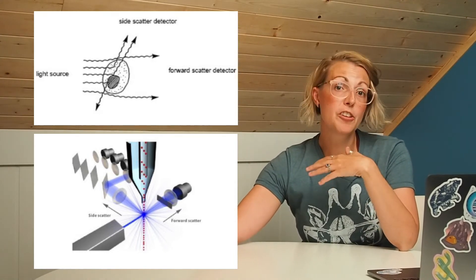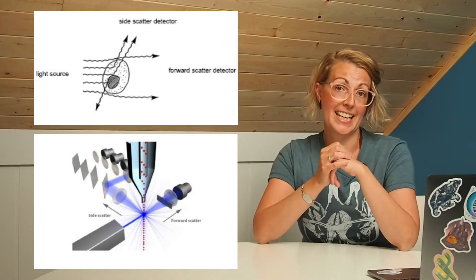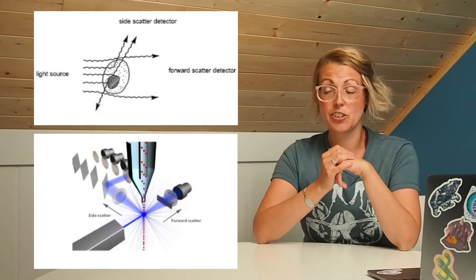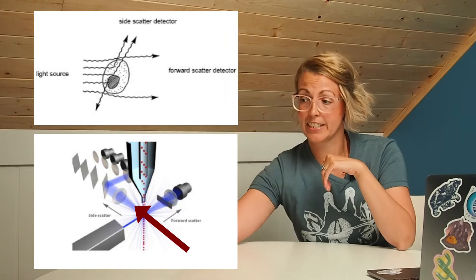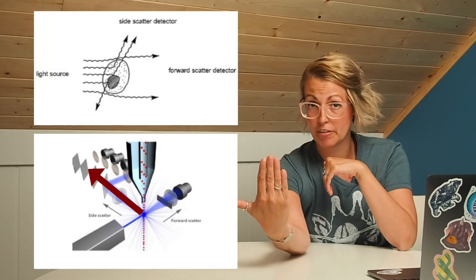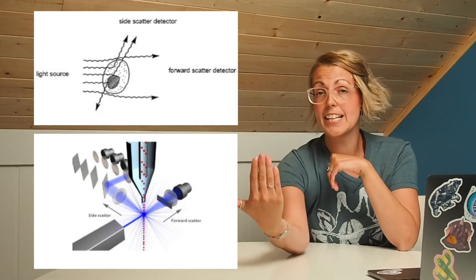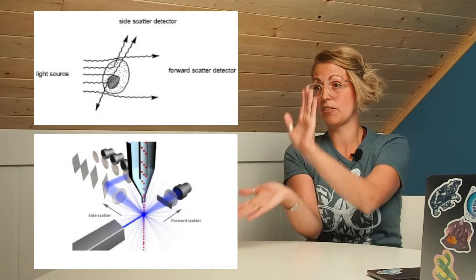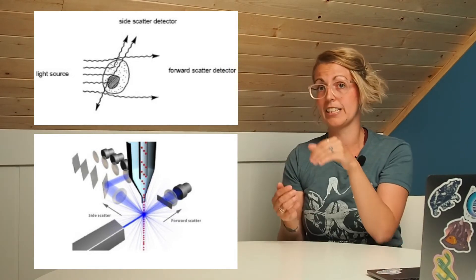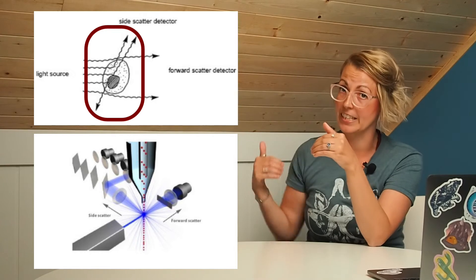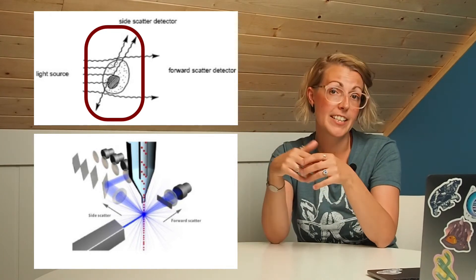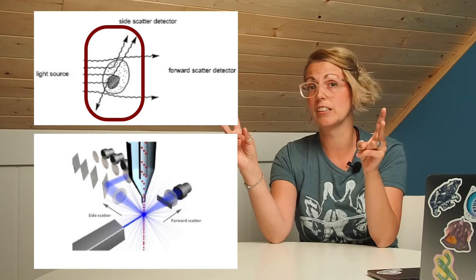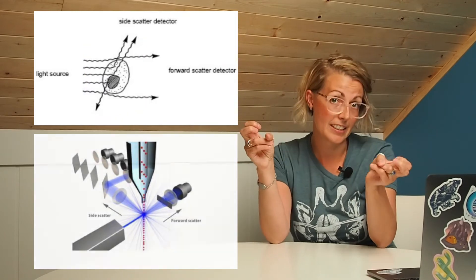The other form of light scatter we'll be detecting is called side scatter and it's called side scatter because the detector is at a 90 degree angle from the light source. On the side scatter detector what we're detecting is instead of the light that diffracts around the cell, we're detecting the light that bounces off things inside the cell. So because of this side scatter is often termed the granularity or complexity of a cell.